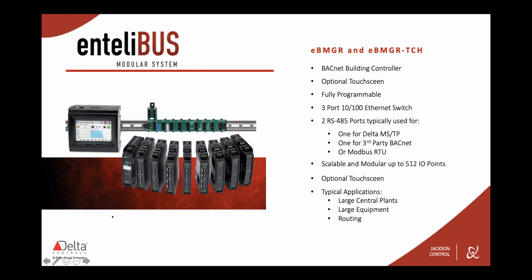I could spend an hour talking about this one, but basically everything can either plug directly into this controller, or you can network out the I/O. In a mechanical room you might have a concentration of points in one area, but an MCC or a bunch of pumps off in the corner. Rather than home-running a bunch of wire back to the controller, you can run a 2-wire network—we use CAN bus for internal communication between modules—and network them out where it makes more sense, keeping some modules remote from the main engine. This gives a lot of flexibility in your install.